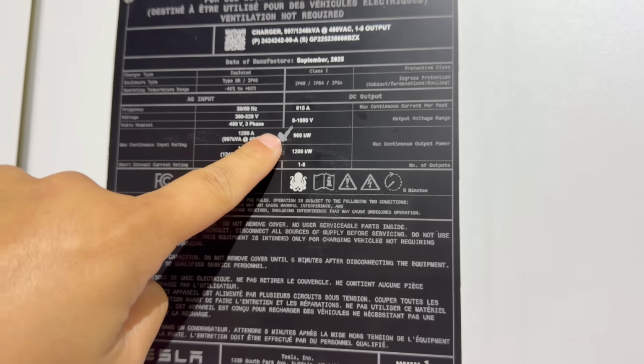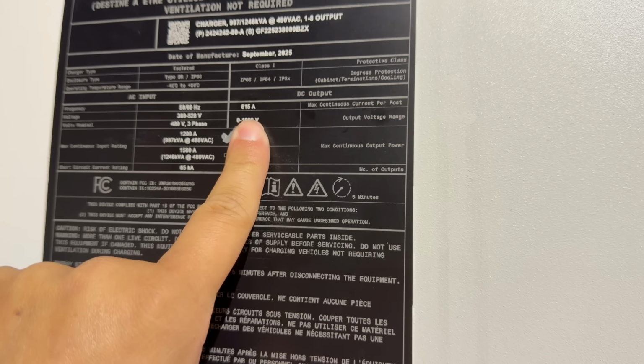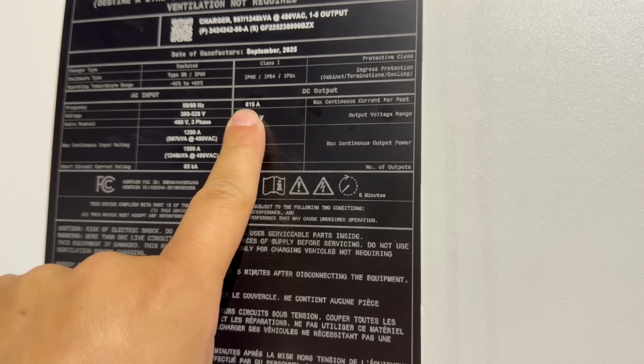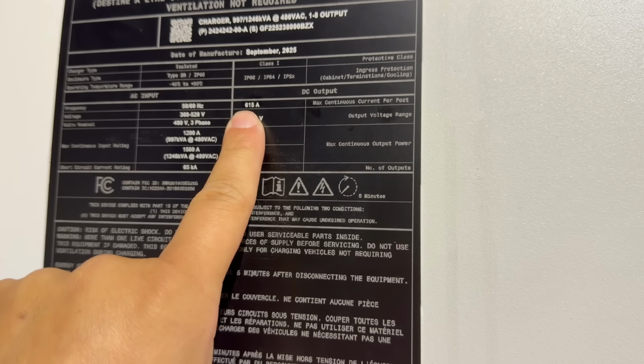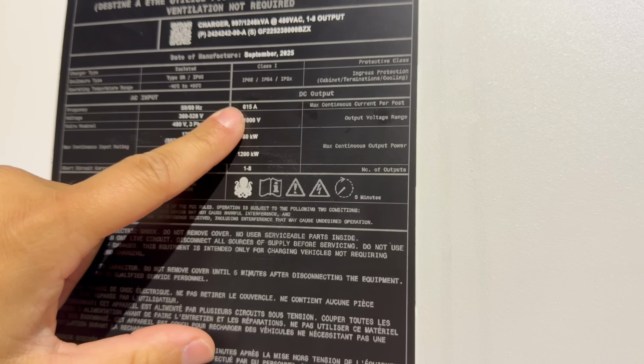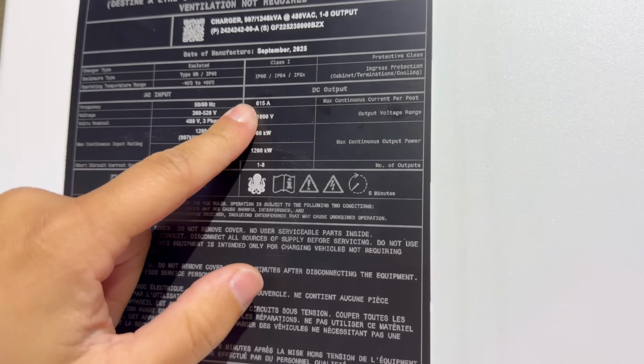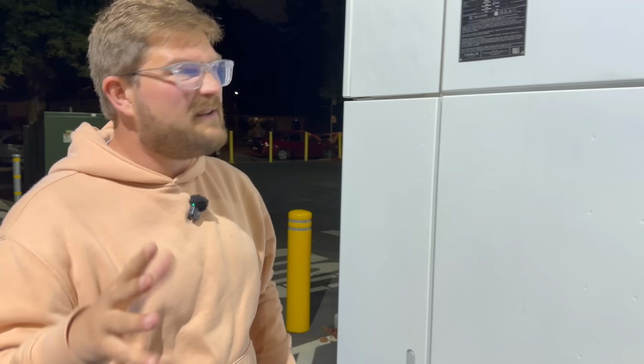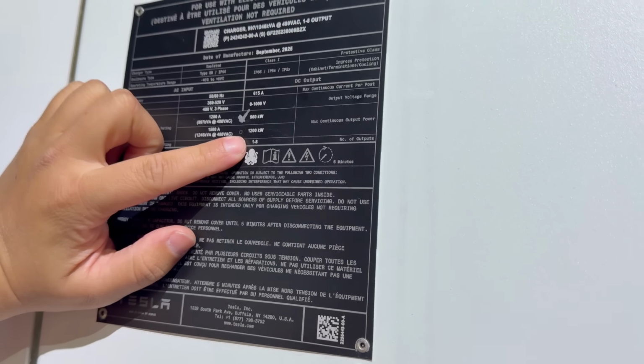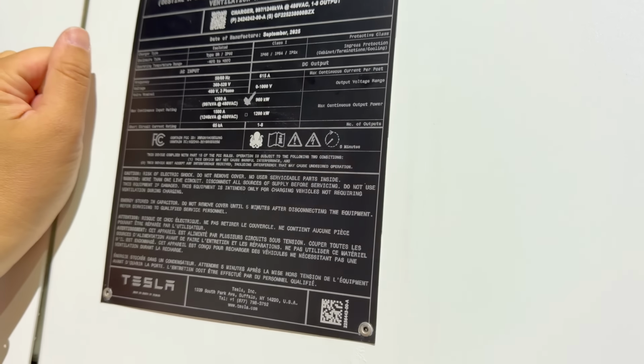It's IP65 rated, IP64 and IP2X. DC output voltage range is 0 to 1000 volts, and max continuous current is 615 amps. Now, we all know Tesla can sometimes go over this. So if you have a low voltage, high current car, like a Volvo EX90, they want 600 amps. And Cybertruck, oh yeah, so I guess low voltage, high current above this would be like Model 3, Model S. They would take at low state of charge maybe 700 amps, they could do that for a burst. And then you can see here, max number of outputs, again, 1 through 8. Wow, very interesting.